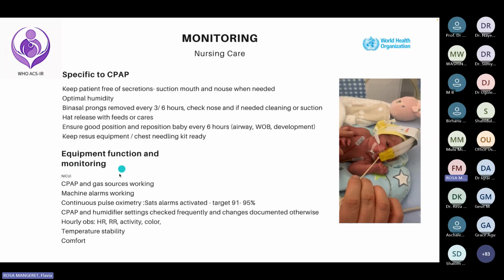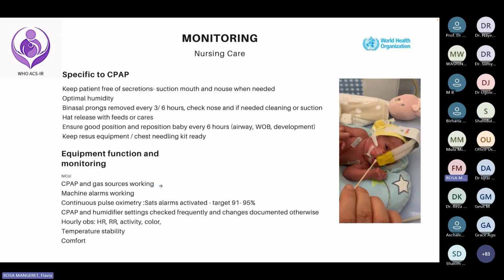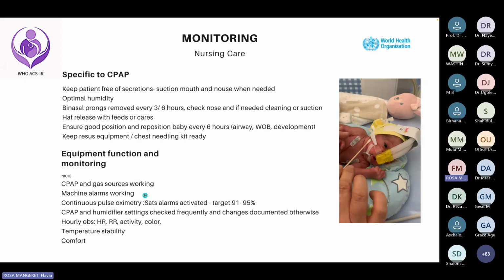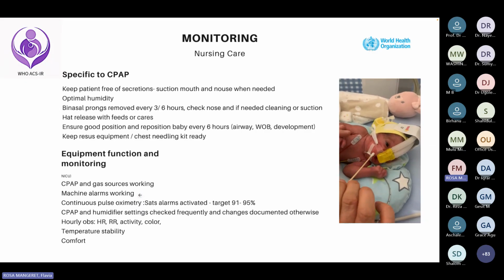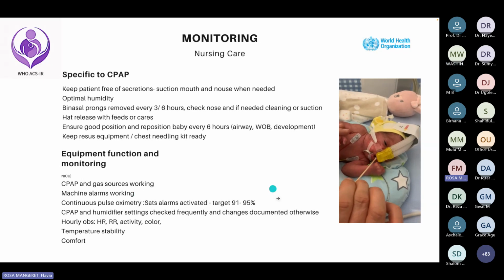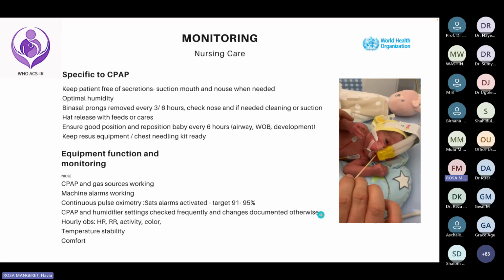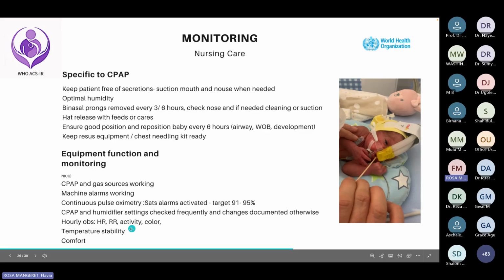Equipment function and monitoring. So CPAP and gas sources need to be working, so this needs to be checked at least every shift and anticipated if there is a need for replacement. Machine alarms: the machines that have an alarm, we also need to check that the alarms are working and set. Continuous pulse oximeter with the SATS alarm activated with the right target for preterms. CPAP and humidifier settings checked frequently and changes documented. Hourly obs for vitals, temperature stability and comfort.